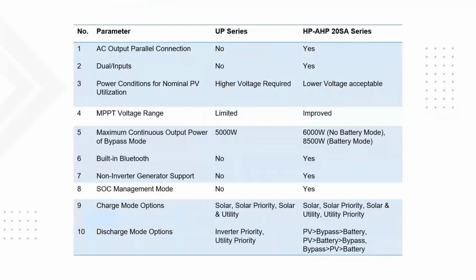Let's look at this table outlining the main differences between the 20SA and the preceding UP series. You'll notice the 20SA has parallel output connection, which the UP series does not. This is important for scaling up power systems—connecting up to 12 units in parallel significantly increases system performance and output, which is important for large scale installations where a single unit's capacity might be insufficient.